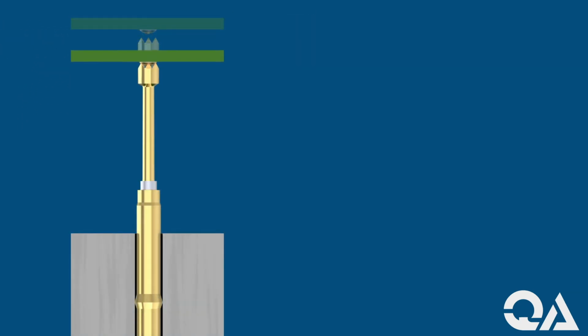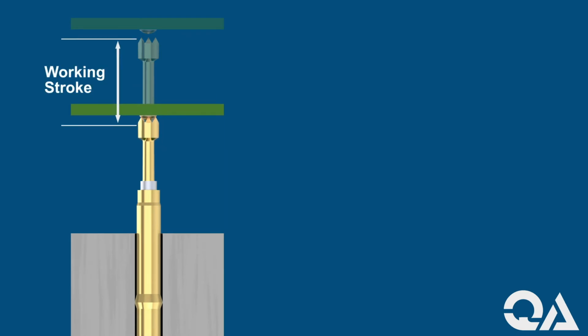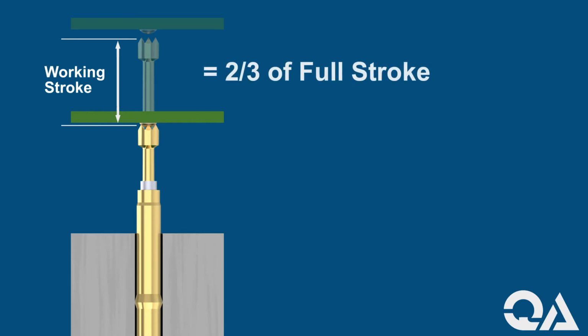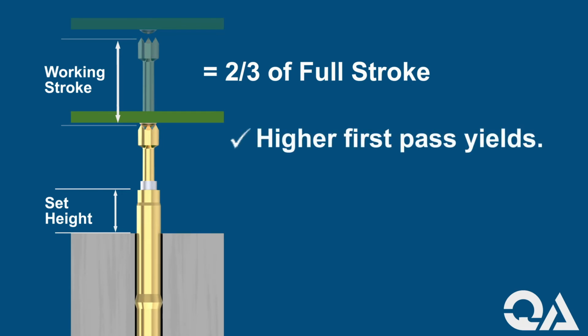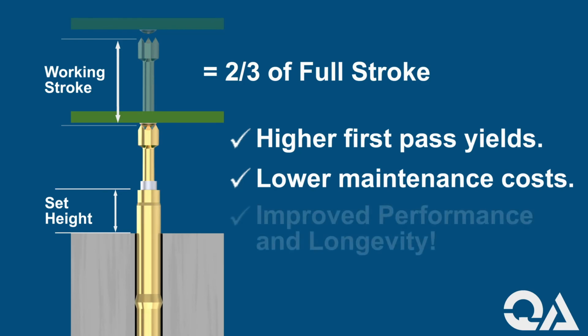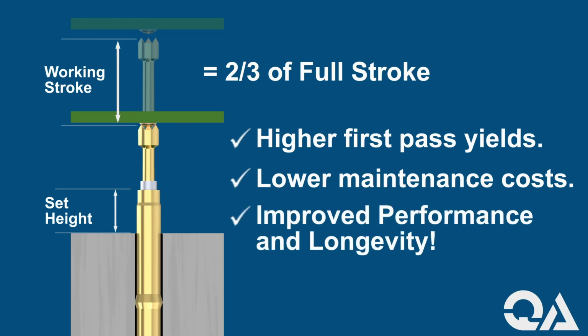In summary, spring test probes are made to be at their designed working stroke when testing an intended target. The working stroke is typically 2/3 of a probe's full stroke capability. Test fixtures should be designed and built so that the sockets or X-probe termination pins are set at the correct height for the probes to stroke the recommended amount when actuated. Setting probes to achieve the proper stroke will increase first pass yields, reduce fixture maintenance costs, and improve the performance and longevity of your test probes.